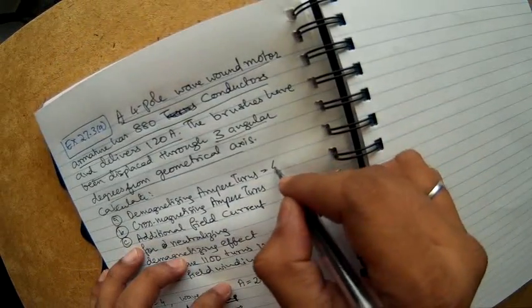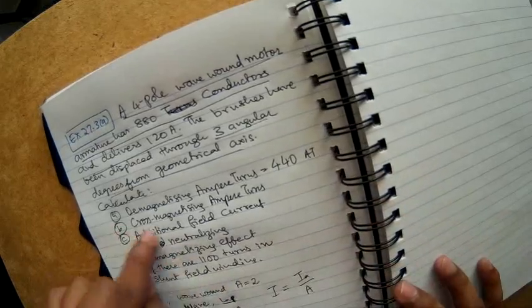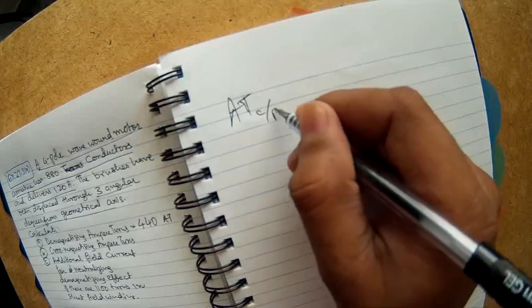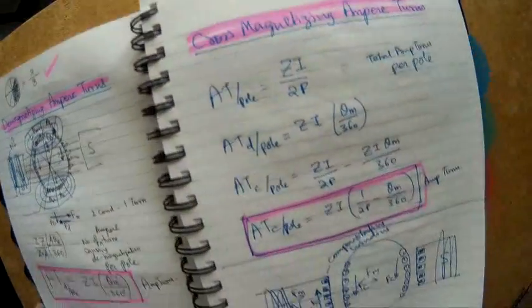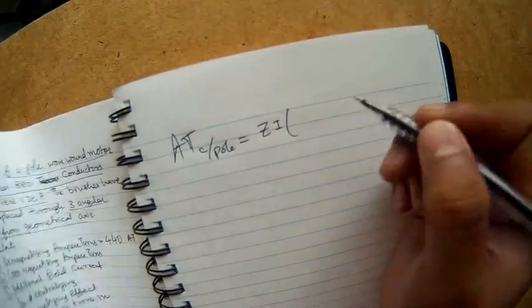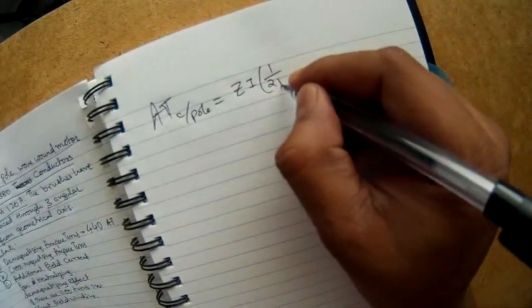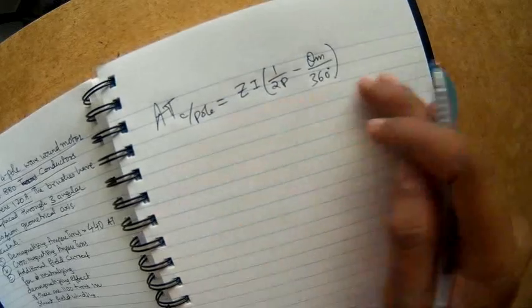So this is the first answer. So answer is 440 ampere turns. Now cross magnetizing ampere turns. Again that is very easy. So ampere turns cross magnetizing per pole. We had just derived the formula in our previous video. So I just copy that formula here. So this is Z I times 1 by 2P minus theta m by 360 degrees.